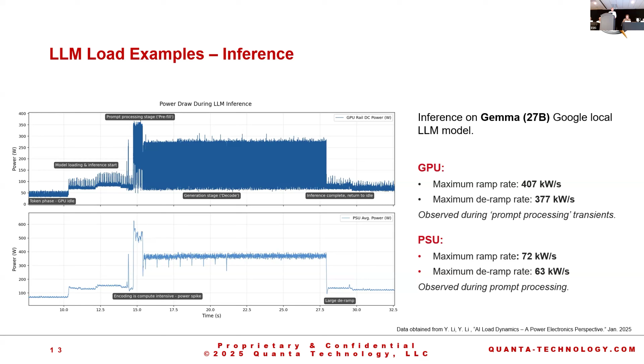Comparing the result, you have 400 kW here compared to 72 at the PSU, and you can see the jump. What I'd like to emphasize again is that for inference, there's a low possibility of having several requests at the same time, and that really helps, because they won't be in phase and create a higher spike or dip.